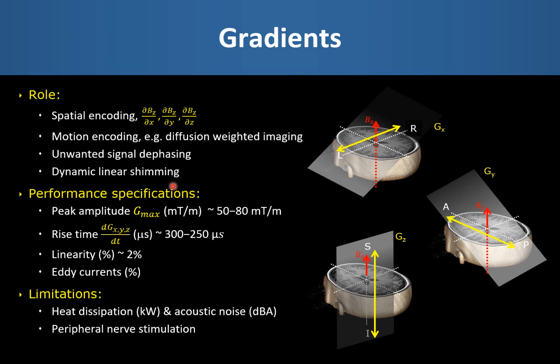In terms of performance specifications, we are looking at the peak amplitude achievable in millitesla per meter, the rise time from 0 to the maximum value typically in microseconds, the linearity of the gradients over a defined field of view, and we are also looking to have minimal interaction with other conducting structures such as a magnet cryostat. The gradients typically induce eddy currents in the cryostat, and the magnetic fields generated from those eddy currents then distort the gradient waveforms. So lots of work goes into minimizing that interaction.